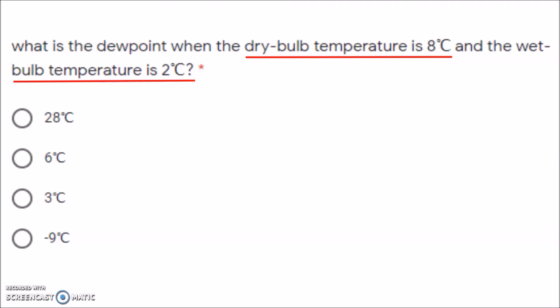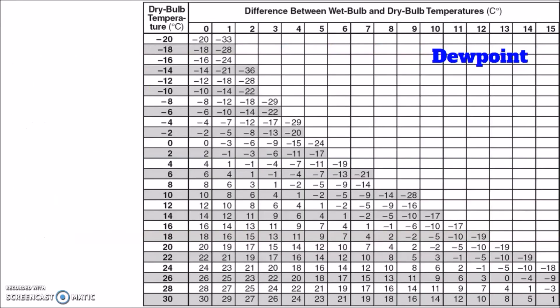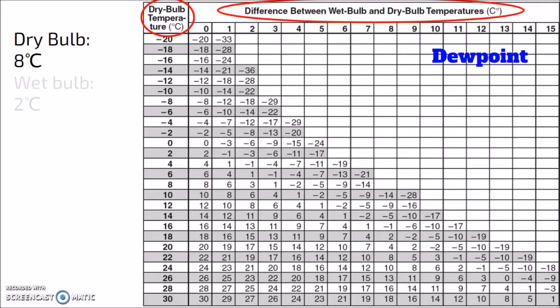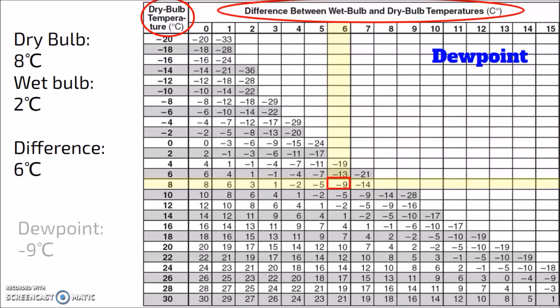What is the dew point when the dry bulb temperature is 8 degrees Celsius and the wet bulb temperature is 2 degrees Celsius? We have a chart that works with dew point instead of relative humidity. The dry bulb is 8 degrees and the wet bulb is 2 degrees, giving a difference of 6 degrees. Looking at the dew point chart, the dry bulb column of 8 and the difference column of 6 overlap at negative 9. Our dew point is negative 9 degrees Celsius — the temperature needed for the water vapor to condense into water.